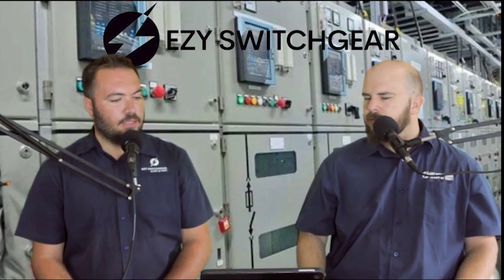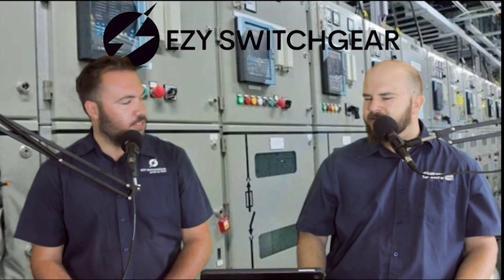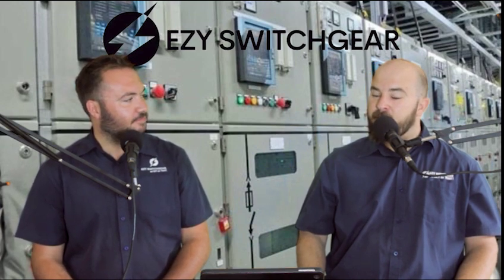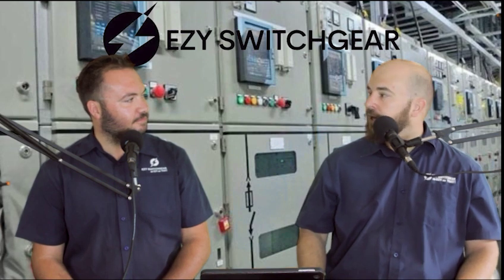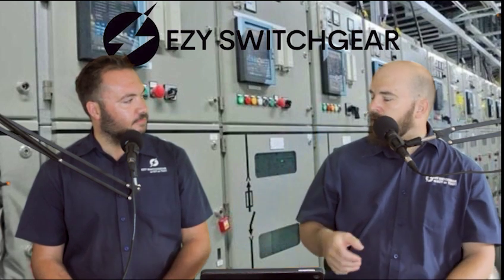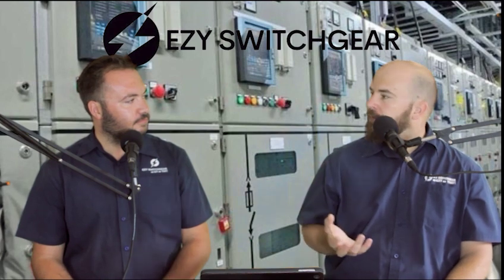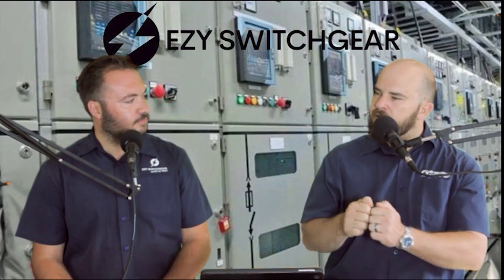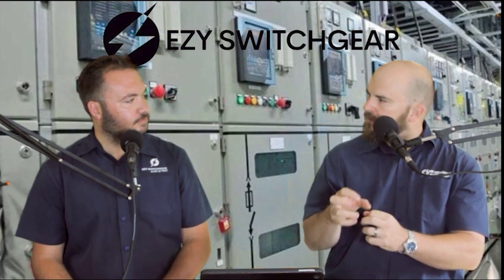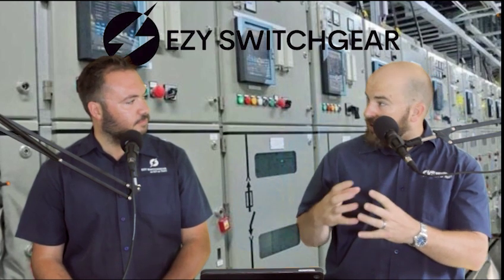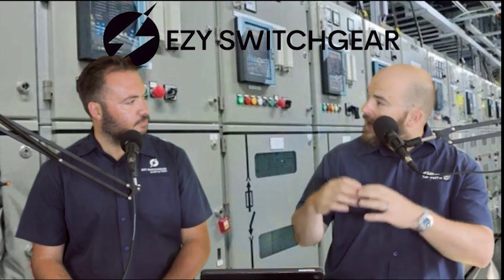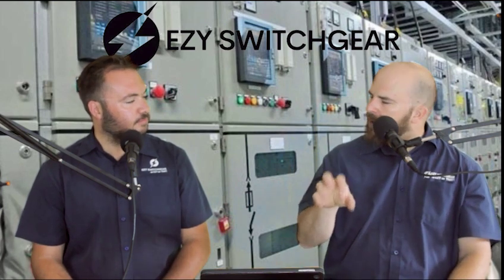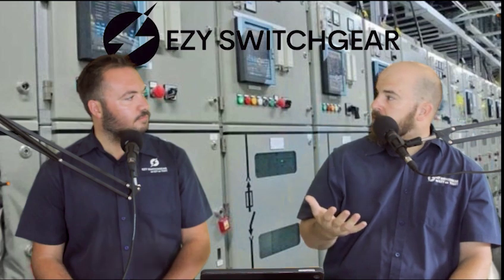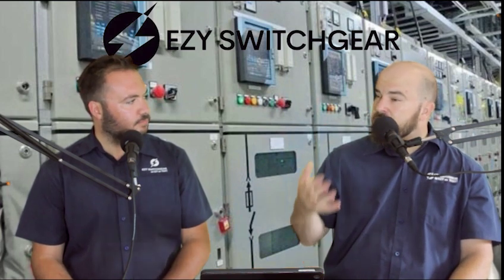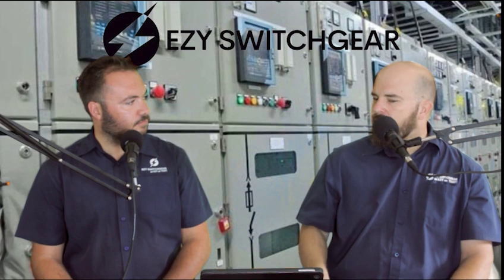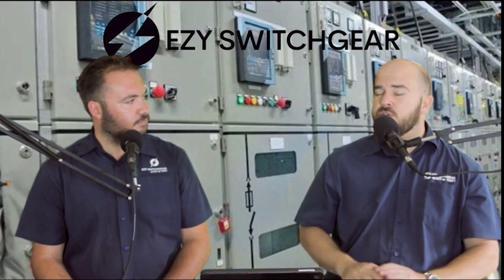Okay. And then the dinosaurs of switchgear, the oil insulated. Yes, that is where everything came from. Oil insulated switchgear is almost like a transformer with oil. It's a cooling mechanism, it's an insulating mechanism. But the problem is that every time you switch, you create small amounts of conductive particles, and there's dissolved gas in your oil. There are all kinds of breakdown effects which cause carcinogens in your oil. The oil needs to be changed every now and then, almost like a vehicle. And if you don't do that, you've got a huge fire risk.